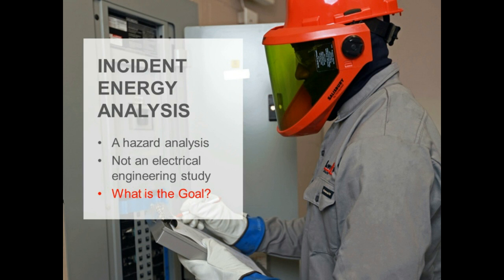70E changes every few years, and in the 2015 edition they moved away from the term arc flash analysis and started using incident energy analysis. There's a good reason for that, which we'll talk about more later, along with categories of clothing and some changes that happened there. But now we're talking about incident energy, the actual calculation of this hazard.